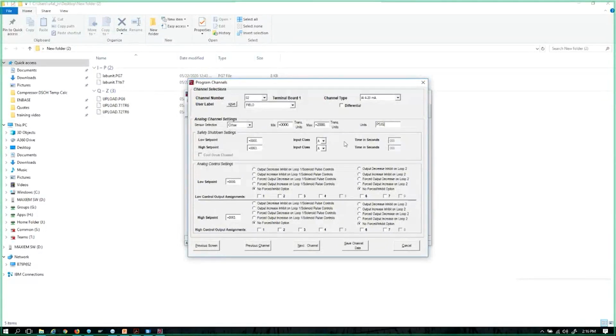Another good example of what we can do with a 4 to 20, and I've done this for several people. Let's say somebody has an H2S site, and they want to add in an H2S monitor. Oops, I do like to use caps lock on this. It just looks better on the screen, I think. So we have H2S, we have other, and now we have to go to the manufacturer that's manufactured the sensor, or the person who's manufacturing the sensors. They're going to have to tell us how this 4 to 20 milliamp H2S sensor is scaled. The most common answer I get when I'm setting these up for people is 0 to 40, and the units of measurement is parts per million.